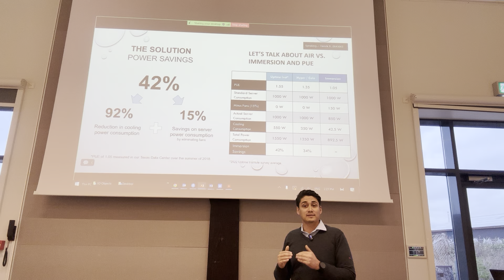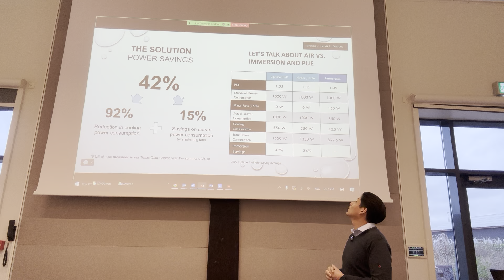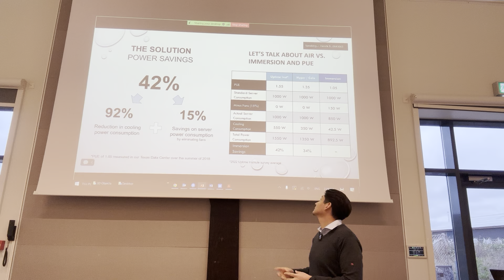You remove that, it lowers your base, and then you start getting efficiencies from PUE because of immersion cooling. Instead of 1.55 or 1.35, you go to 1.05, and we've measured this, we can justify that number. Your power consumption for a standard 1,000 watt server goes from almost 1.5 kilowatts or 1.3 to less than a kilowatt, because we remove those fans and have a very efficient cooling system. Again, we're only assuming 15% for the fans, which is a pretty conservative average. Savings could be larger than that.